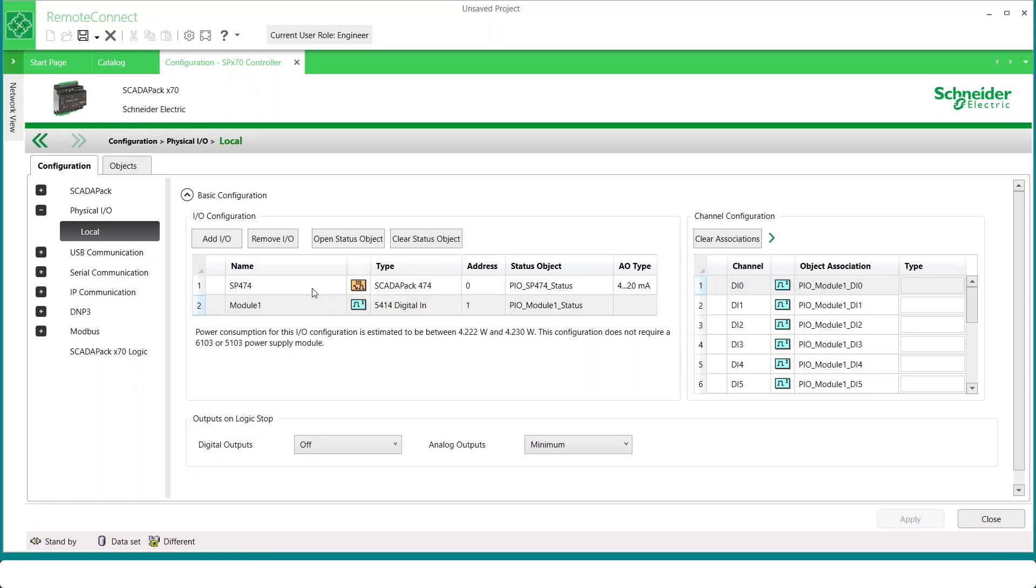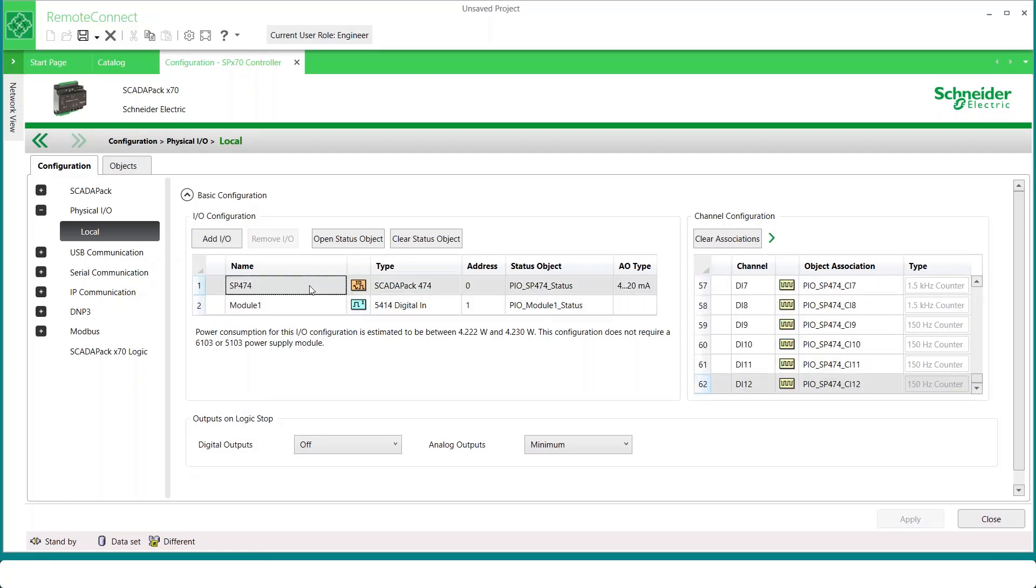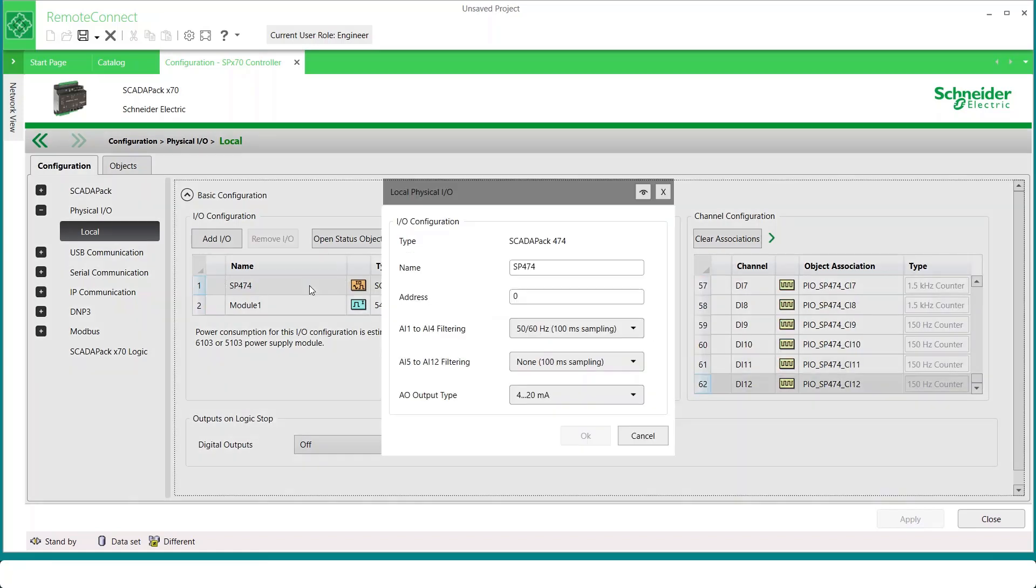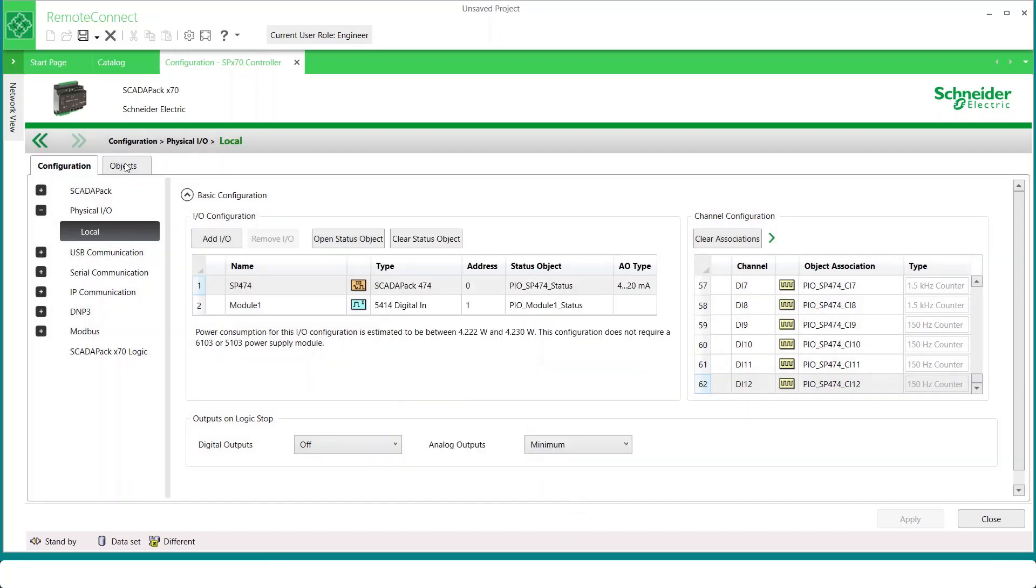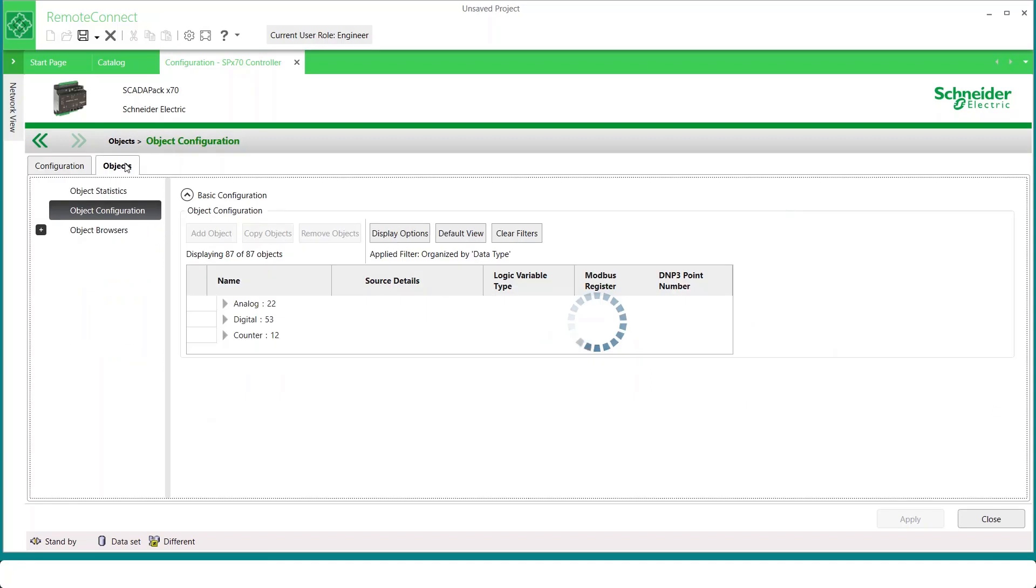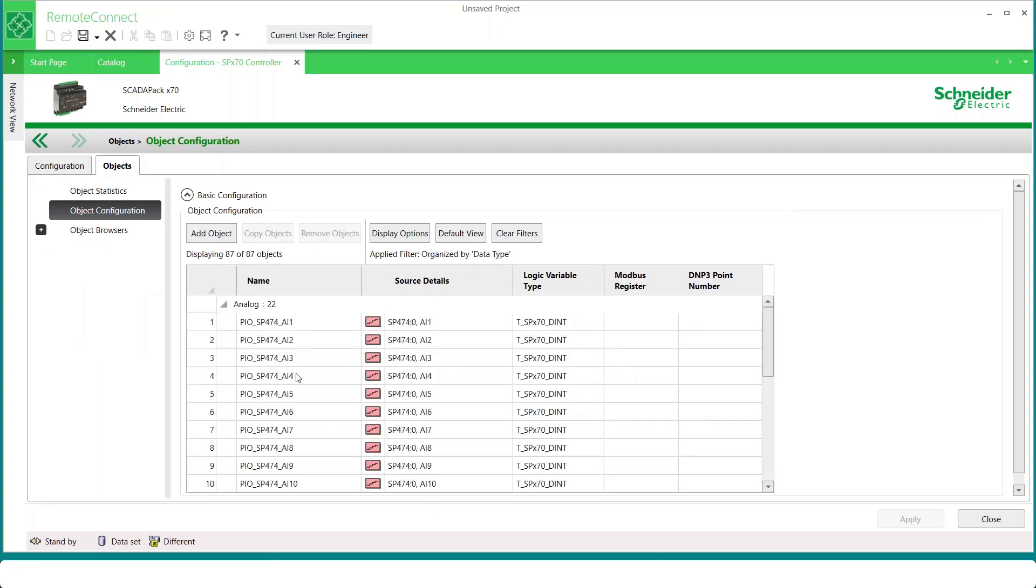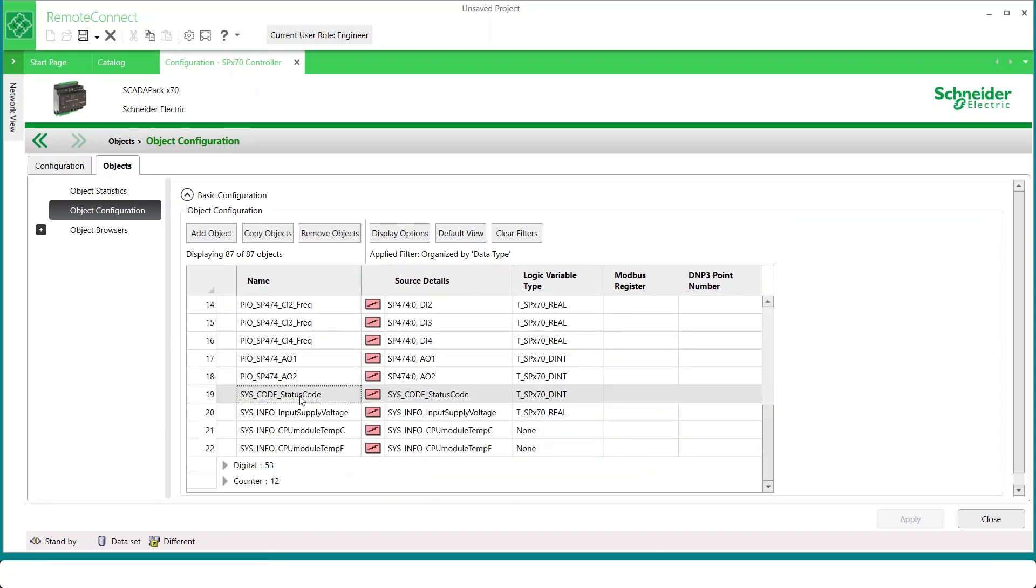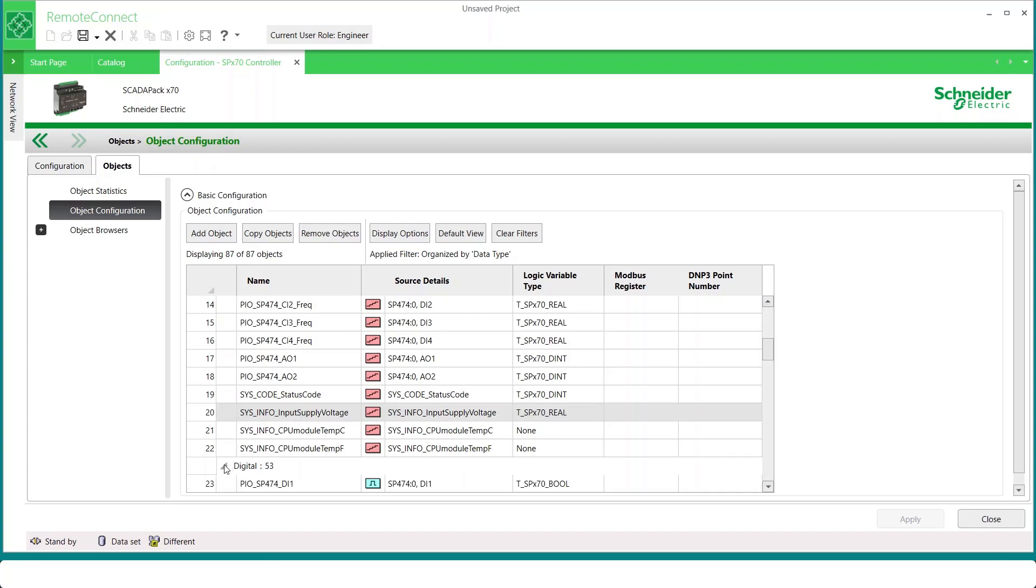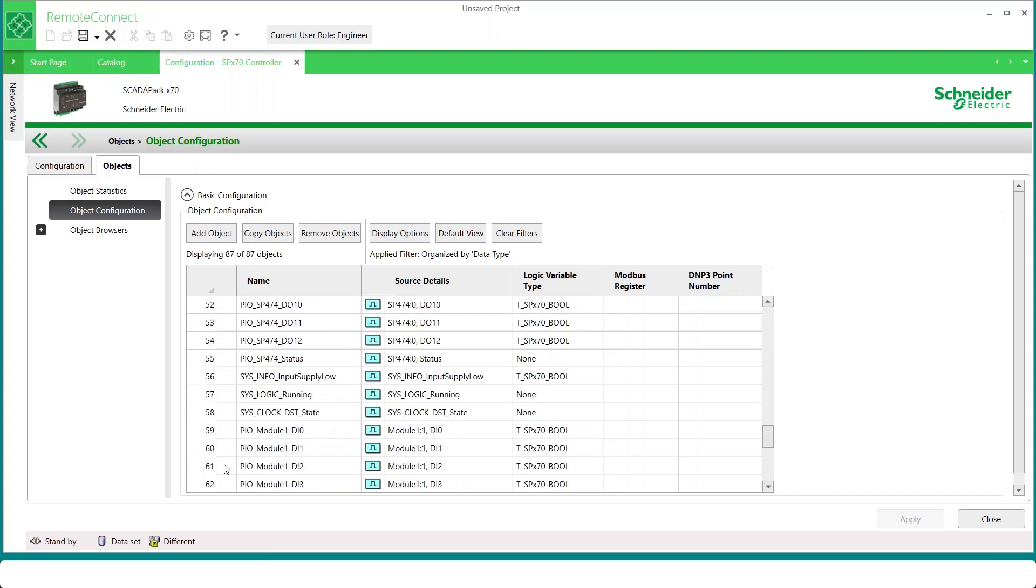While we're here, we can also double-click on the SCADA pack itself and see that it has configurable parameters as well. For example, input filtering and analog output type. On the Objects tab, we can see all of the physical objects created by this project. If we expand the Analogs group and scroll down, a few additional objects can be seen. These are automatically created analog status objects tied to the physical I/O board. In this case, the board's status code, the temperature, and the supply voltage. We can also expand the Digital section and see that there are status parameters in the Digital section as well.